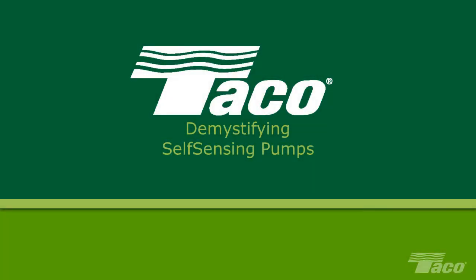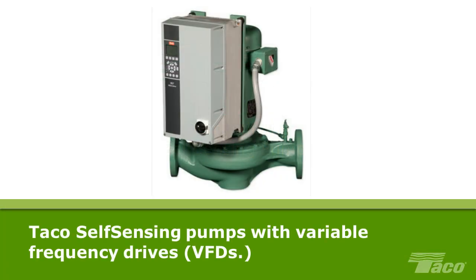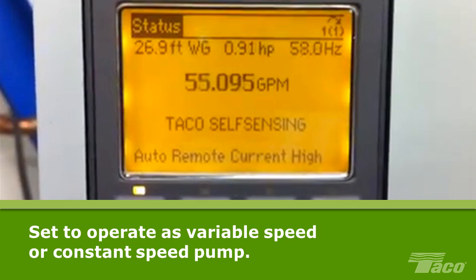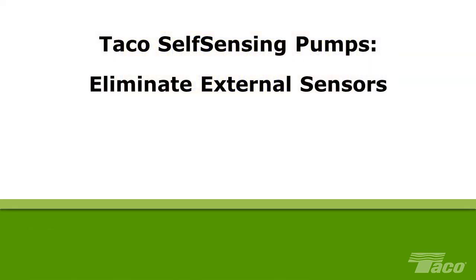Demystifying self-sensing pumps. Variable speed pumping is bringing new levels of efficiency to the HVAC industry. The most recent innovation to this powerful technique is the family of Taco self-sensing pumps with variable frequency drives, VFDs. Users can set up a Taco self-sensing pump to operate in one of several variable speed modes or at a constant speed. These pumps eliminate the cost of external sensors.